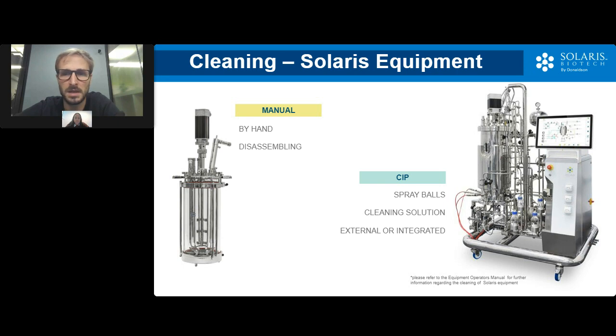Spray balls will be introduced in dedicated ports on the vessel and clean the internal part of the vessel through the recirculation of a pressurized cleaning solution. Positioning of the spray balls is fundamental to avoid creating shadow areas due to the presence of bioreactor components such as shaft, impellers, sensors, and so on. We offer two different solutions for cleaning-in-place systems. They can come with an integrated CIP solution, which will use the vessel as the preparation tank for the cleaning solution. Or the bioreactor can be configured to work together with an external CIP.